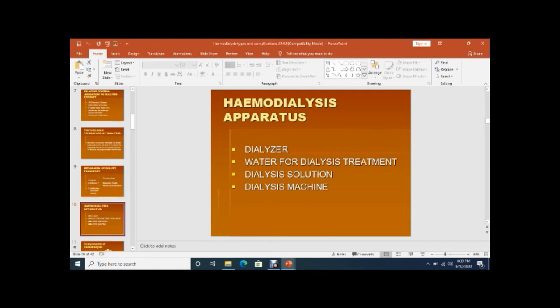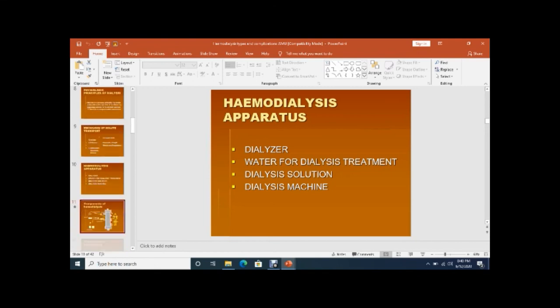The apparatus for hemodialysis requires a setup present in the hospital — a dialysis hall with an RO system, various dialysis machines, a dialyzer, purified water for treatment, dialysis solution, and the dialysis machine itself. These are the components of hemodialysis.